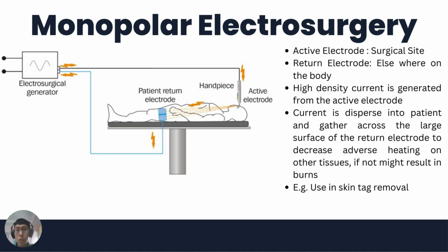There are two types of functions for the electrosurgical unit. They operate differently from each other: monopolar and bipolar electrosurgery. In monopolar surgery, the active electrode is positioned at the surgical site, while the return electrode, also referred to as the dispersive pad, is positioned elsewhere on the patient's body. The surgical effect is produced by the high density current at the active electrode site.